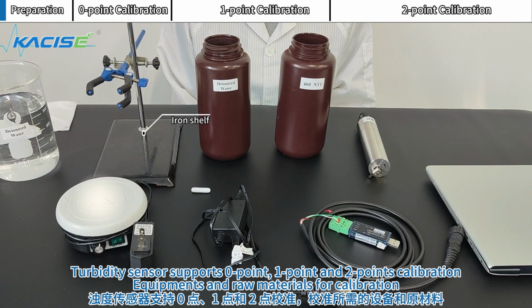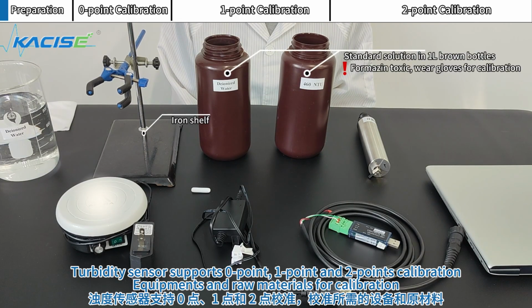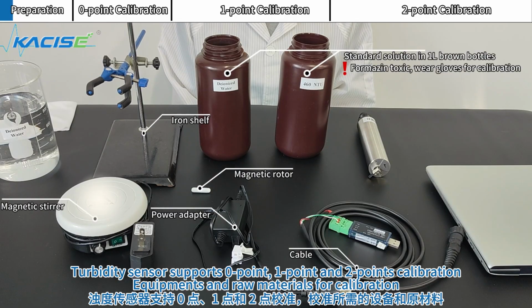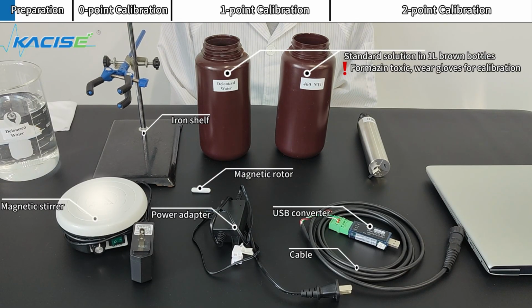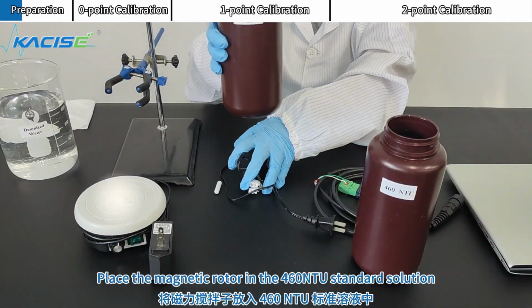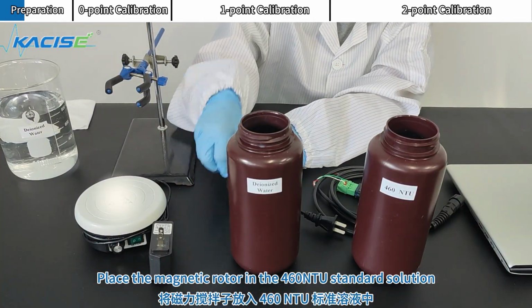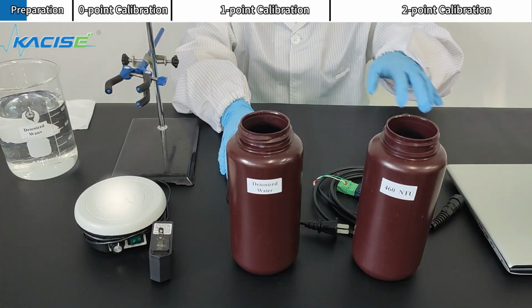Turbidity sensor supports 0 point, 1 point, and 2 points calibration. Equipments and raw materials for calibration. Place the magnetic rotor in the 460 NTU standard solution.